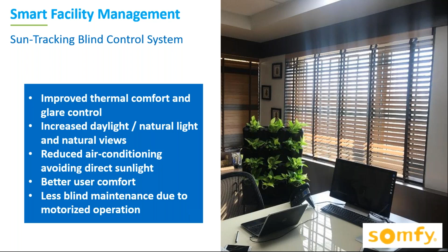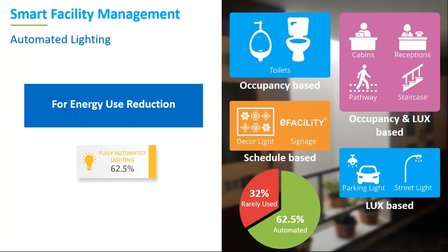On lighting, a lot of companies use occupancy sensors, but we automated most of this further — apart from occupancy sensors, we also use lux-based management of individual lighting. People can control the lux level they need, and the lights operate accordingly. Today 62.5% is fully automated: toilets are fully occupancy-based, while stairways, pathways, reception, cabins and other areas are occupancy and lux based, so the occupancy sensor only activates once lux levels go below a certain level. That's a new thing we implemented.